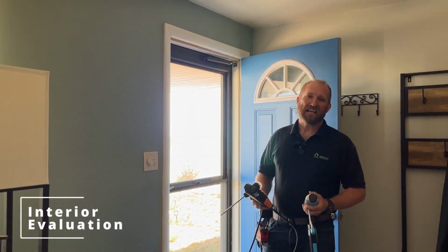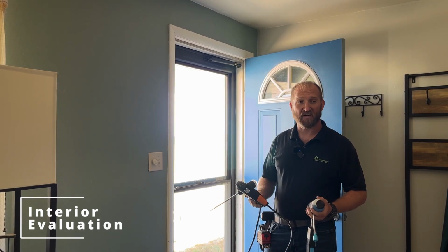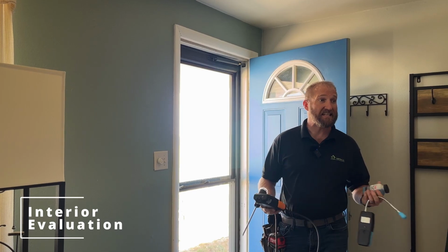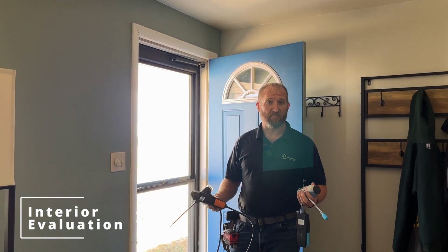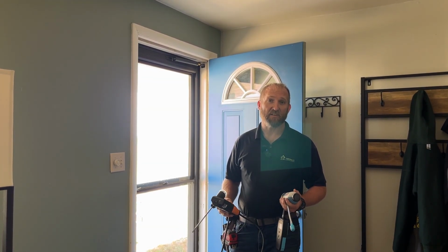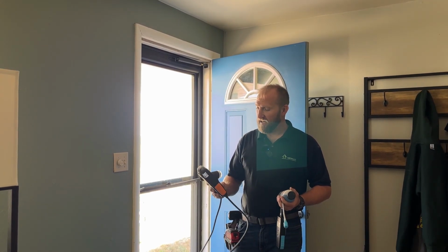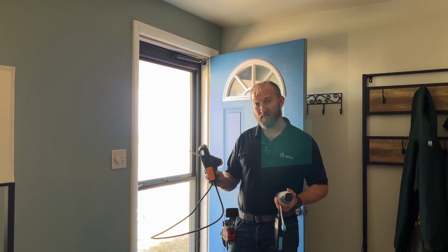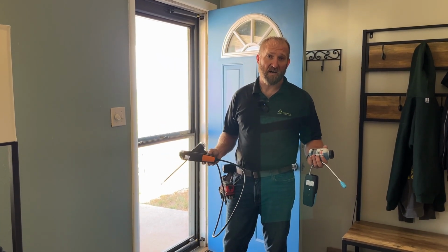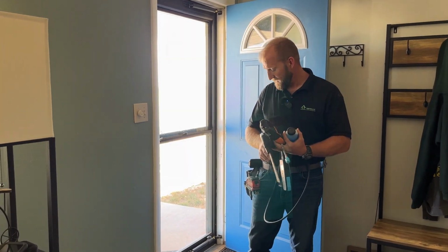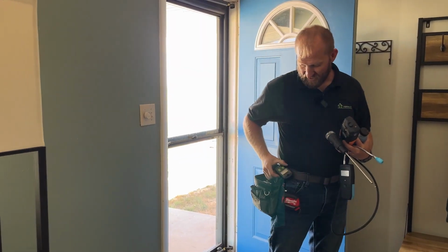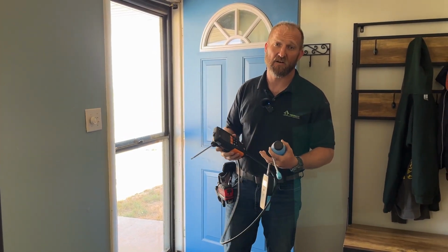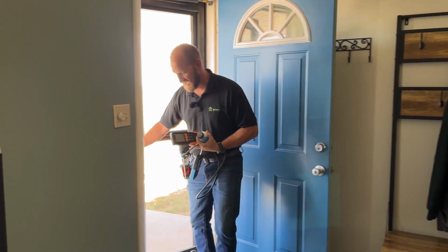All right, so what we will do too is take a reading from our gas sniffer or combustible gas detector inside the house to make sure that our levels are below the BPI standard of 10% LEL, the lower explosive limit. We're also going to make sure we zero our combustion gas analyzer outside to check for carbon monoxide in the house. We also will always check with our personal device that should read what the ambient CO levels are in the house. I'm going to place this outside real quick and start it up.